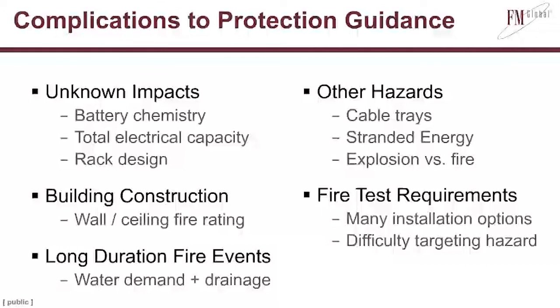Codes or standards like NFPA 855 say if you want to have a larger energy storage system in a room, or you want to adjust the recommended separation distance or protection, then you need to run a large-scale test. From what I can tell, every energy storage system looks different. The installations, the way they're deployed, can all be very different, with huge variations from indoors to outdoors, no doors, doors, one rack next to each other, a bunch of racks next to each other. And because there are so many installation options, it can be very difficult to target the hazard. So all of these tests have to be designed very specifically, and there's no one-size-fits-all test.